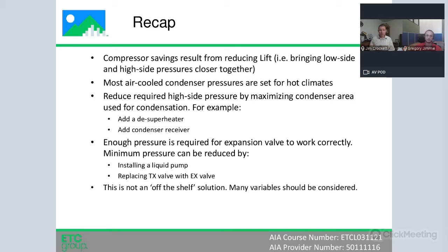You want to maximize the area in your condenser available for condensation, because that allows you to run at a lower pressure. You can get that by adding a desuperheater to buy some room at the top, add a receiver to buy some room at the bottom, and you've got to keep your pressure high enough for the system to still work. That is all I have.